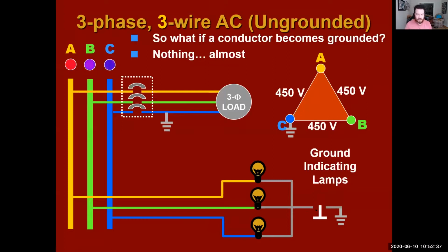So what they did is they added this switch so it removes the ground. So you no longer have a wire connecting the two ends. You basically opened up the circuit, and now these 3 lights all become on. Now you know you have a ground.